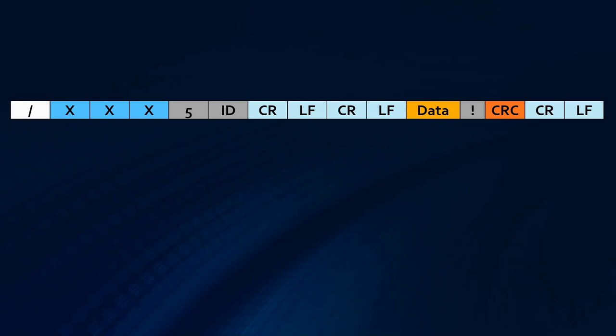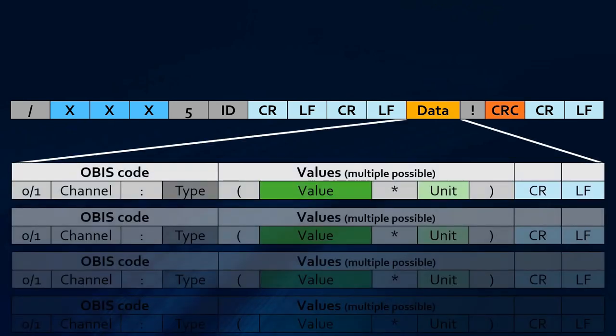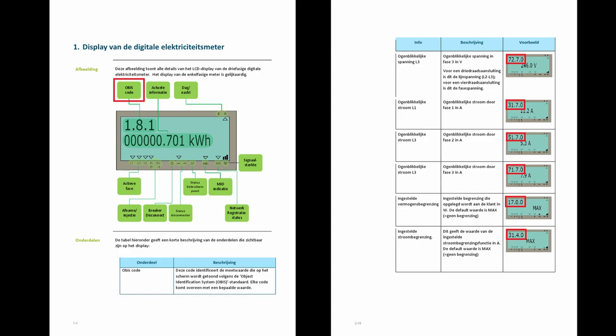Each block of info starts with a slash, and after the start there is a fixed three-digit model-specific identification. Then we have the letter 5 and another three-digit fixed device-unique identification. Next we have the data itself, which consists of several lines, and the message ends with an exclamation mark followed by a CRC code — specifically a CRC16 calculated value of the rest of the block. The data lines start with an OBIS code which has a channel number and type of data for that line, followed by the actual value between parentheses, and if a unit is present it is separated by an asterisk. The meaning of those OBIS codes can be found in the documentation, but it's not always easy to find.